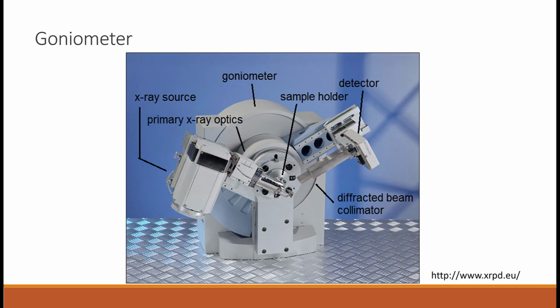There are several types, well, really two primary types of diffractometers in their settings. This is one type here that has 2 moving arms on its goniometer. The instrument we have in our lab has 1 moving arm. Just the detector and the stage move. But both work the same way. What we really need to know is that angle of movement, theta, and we need to know the distances involved, and that's, of course, set up ahead of time.